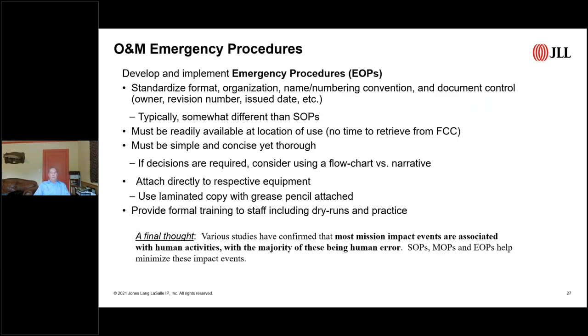So develop your emergency procedures, again in a standard format. But in this case, they don't necessarily look like the operating procedures, standard operating procedures, normal procedures, or maintenance procedures. Emergency procedures need to be very concise and located at the place of use. You don't want to have to go to the command center to find an emergency procedure. It should be at the chiller or the UPS unit or the generator, and it should be laminated or some other means so that you can take notes right on it with a grease pencil or something like that.